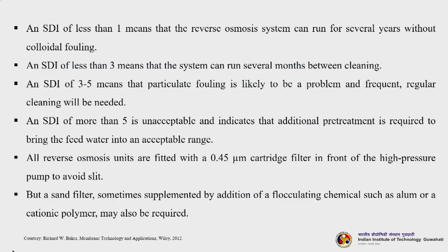An SDI of less than 1 means the reverse osmosis system can run for several years without colloidal fouling. An SDI of less than 1 is usually better and recommended. An SDI of less than 3 means the system can run several months between cleaning, and an SDI of 3 to 5 means that particulate fouling is likely to be a problem and frequent and regular cleaning will be needed. So, now you understand the importance of SDI and why we should measure it. An SDI of more than 5 is unacceptable, and indicates that additional pretreatment is required to bring the feed water into an acceptable range.